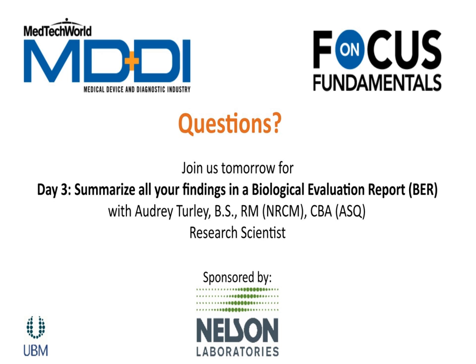Now, these are used in place of a NOEL. They evaluate all of the literature that's available for the compound at one time. They get a major group together and decide what the limit should be, and these exposures would be in humans. What is a safe exposure in humans? Another really great resource is NIOSH, the National Institute of Occupational Safety and Health. A lot of these compounds coming off the device, we also have workers being exposed to, and we can look in the literature to see how humans have been evaluated for these exposures. So that's just to name a few, but there are quite a few.